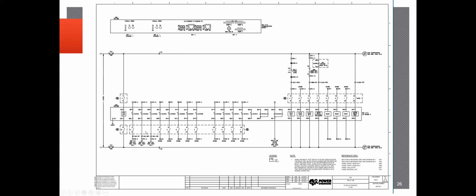Your breaker failure initiates, like we discussed earlier, will be your second step, and any other various outputs that may be associated with it, whether that be alarms or communication trips as well. They can have physical contacts coming out of this relay, going back to the communication-based tripping devices. And then you finish out all your outputs before you move on. So once you get all those isolated, realistically, there's no way that this relay can directly cause an inadvertent trip to any devices. Again, there may still be communication-based tripping that's not associated with a physical output, and it could be just all internal stuff on the relay. So that's why we follow these steps to a T.